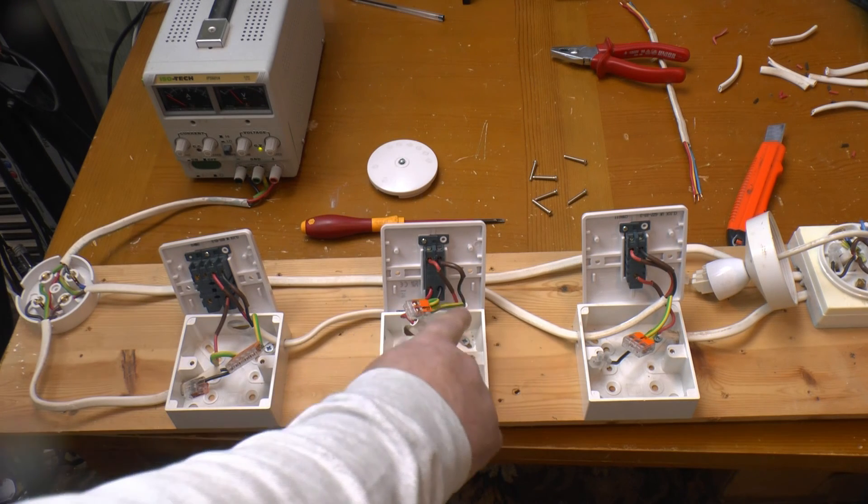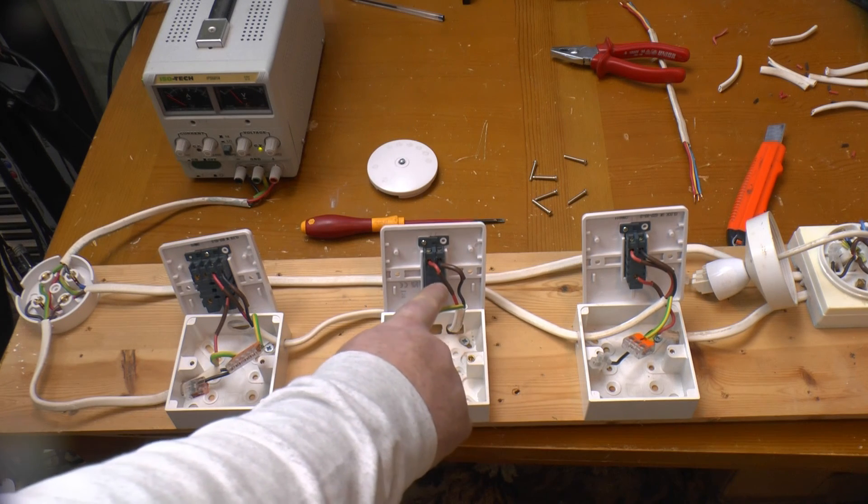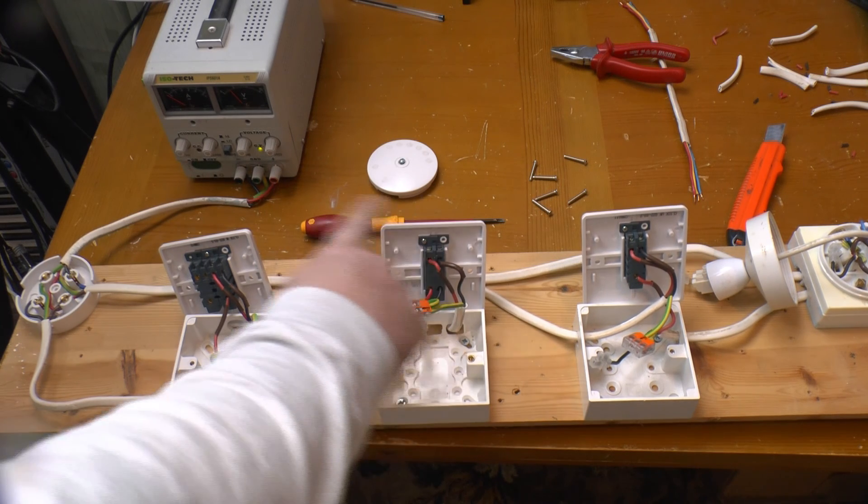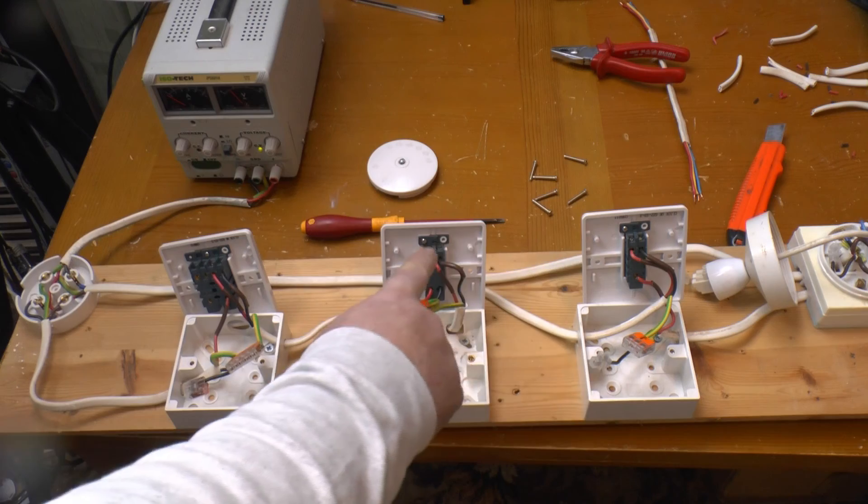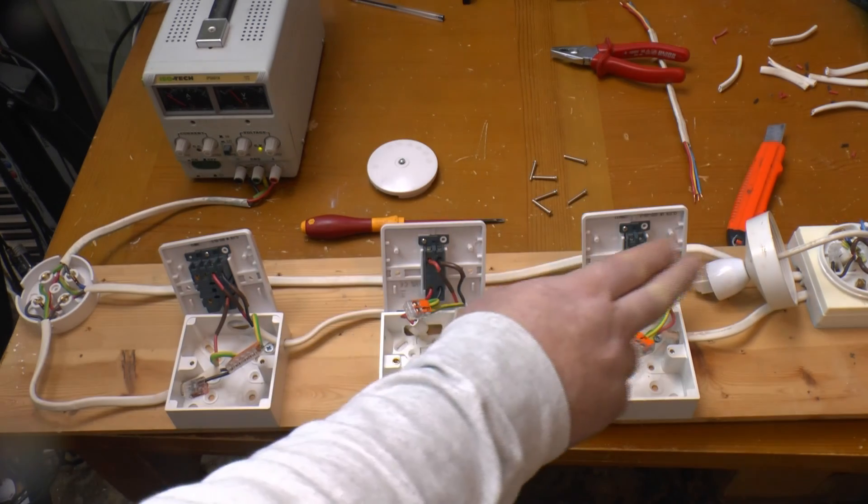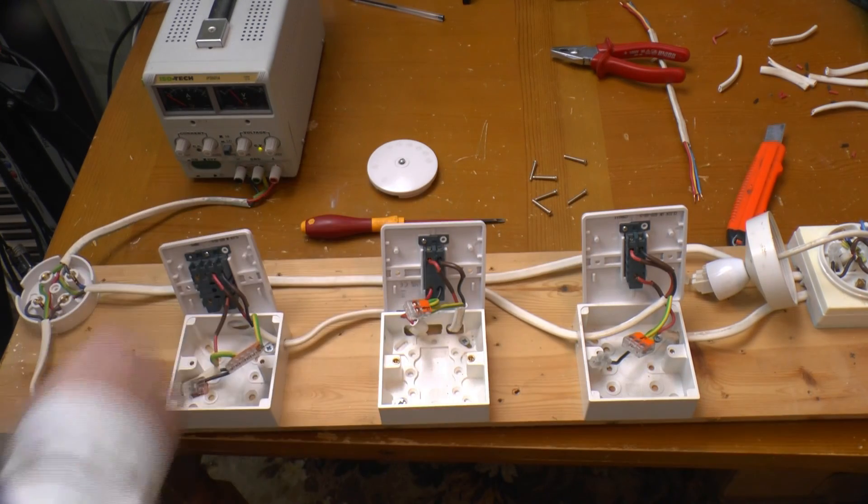Getting the connections wrong on the intermediate switch this time, would result in the intermediate overriding the other switches, and locking the light off, because there'd be no path from one end switch to the other.